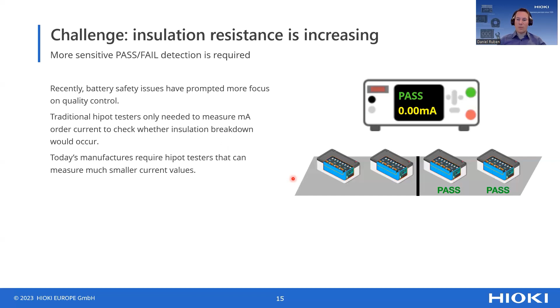In order to understand the higher insulation resistance, the necessity is to have smaller current values to be monitored and to be displayed. And that is why our engineers came up with a device which has a much higher resolution, and this is 1 nanoamp, 0.001 microamps. So this gives a much better and more sensitive possibility to not only have a pass-fail based on the 2 digits after 0, but 3 digits to identify if you have any problems with leakage current.